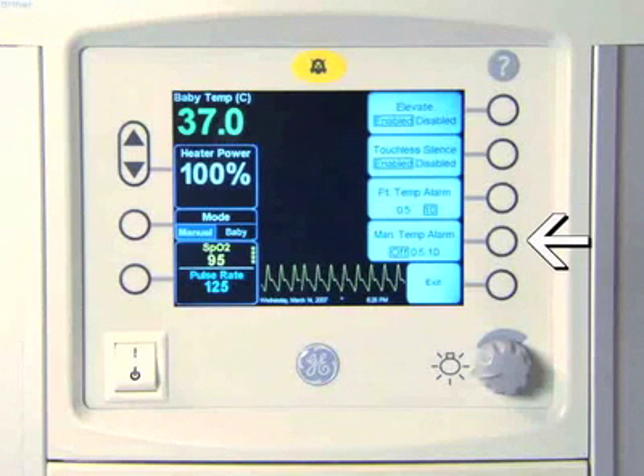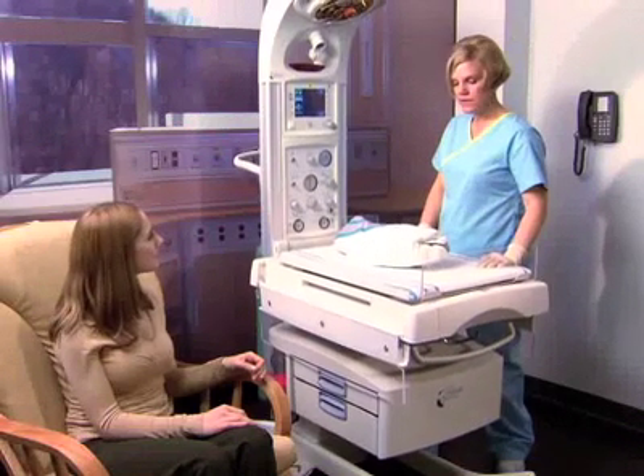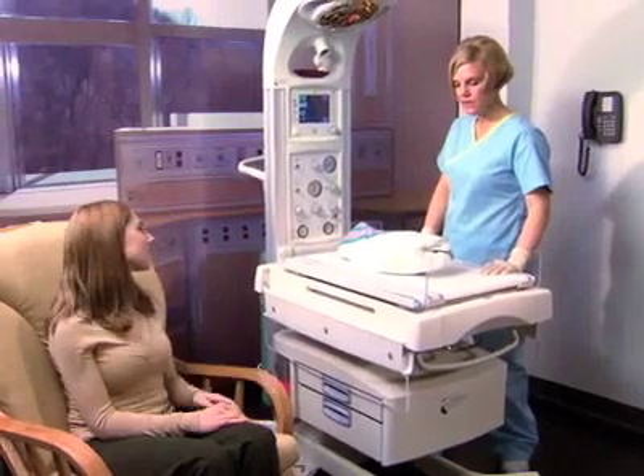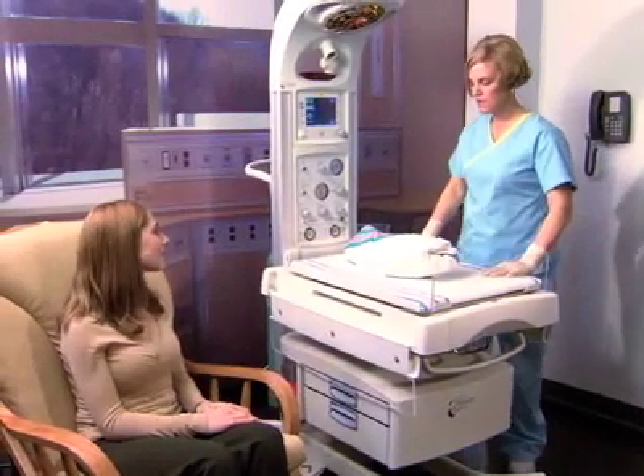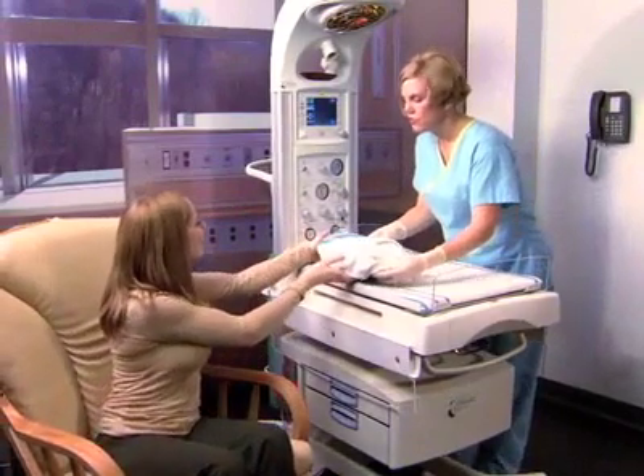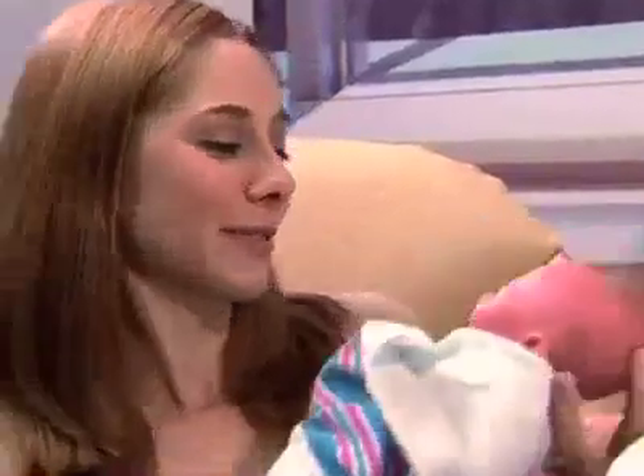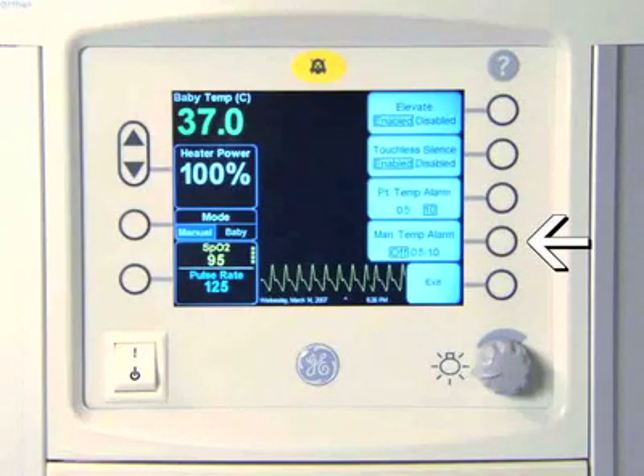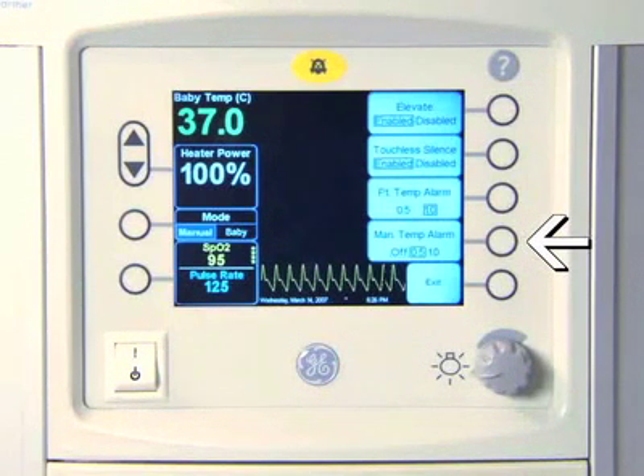The manual temperature alarm is a safety feature that allows you to monitor the baby's temperature in manual mode with a skin temperature probe, and provides you with the safety of an alarm should the baby's temperature reach a range of clinical concern. To set the manual temperature alarm, attach a skin temperature probe to the baby. Push the manual temperature alarm key to choose from three settings in the PandaWarmer's manual mode: off, 0.5 or 1 degree Celsius.